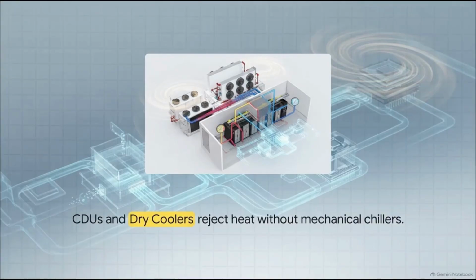This completely shatters the decades-old myth that a data center has to feel like a walk-in freezer just to be efficient. Because the servers can happily accept this warmer coolant, facilities can skip those power-hungry mechanical chillers entirely and simply use large outdoor dry coolers to reject the heat directly into the ambient air. For most climates, this means you can run the facility almost the entire year, utilizing warm summer air to adequately cool the water loop. It is incredibly efficient.